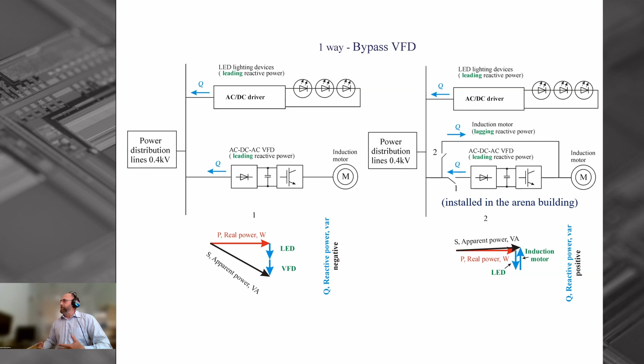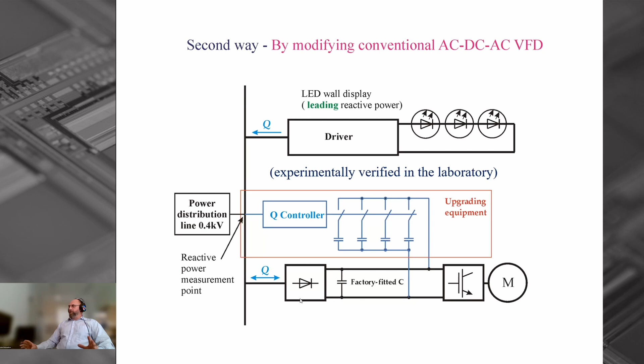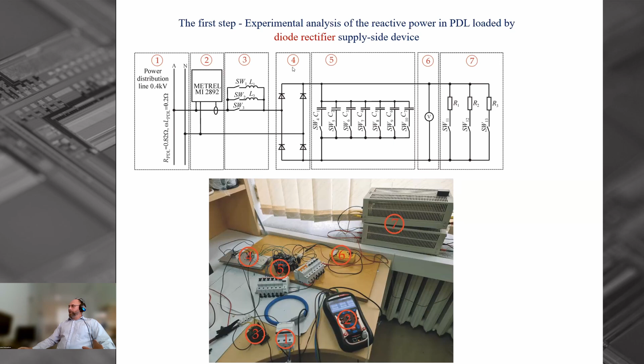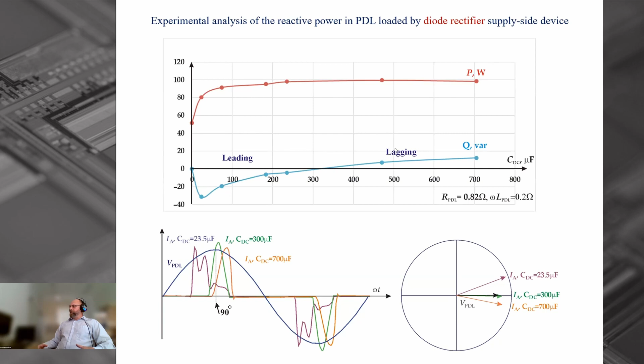The second way is by modifying the conventional variable frequency drive. The conventional drive consists of a rectification stage and an inverting stage, and it has an intermediate DC circuit with some capacitors for filtering. By upgrading some equipment and putting more capacitors in this circuit, we can use it as a reactive power compensator. To prove this, I made some simple experiments. The first experiment consists of researching the situation of a conventional single-phase rectifier and capacitor banks. The results show that by changing the value of the capacitance, we can get leading reactive power at the point of connection to the power distribution lines, and also lagging reactive power. This means that this device could work as a reactive power compensator.